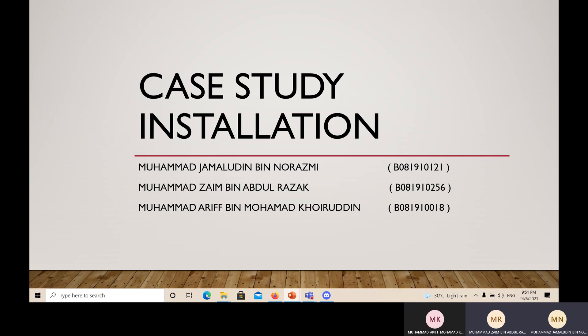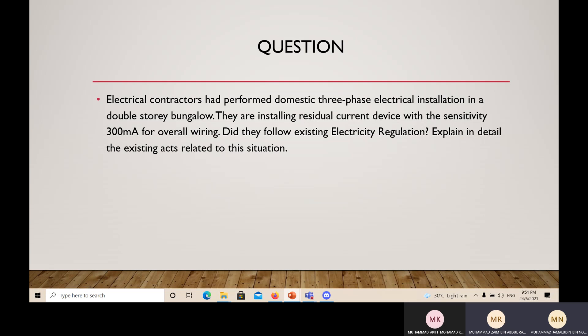This is our question. An electrical contractor had performed domestic three-phase electrical installation in a double-story bungalow. They are installing a residual current device with a sensitivity of 300 mA for overall wiring. Did they follow existing electricity regulations? Explain in detail the existing acts related to this situation.